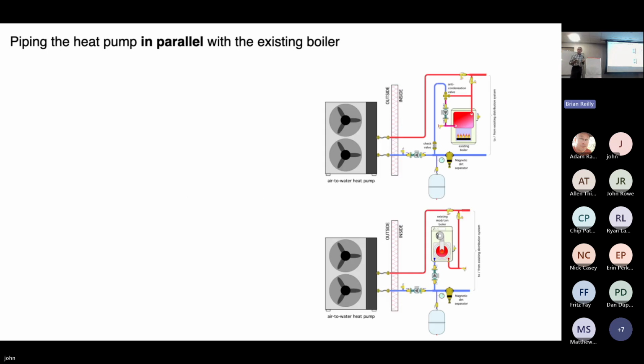John, may I ask a quick question? Sure. Maybe not quick, but if we can't get to it now, I'd love to address it at some point. You showed a slide. We have these dual fuel systems. So we're keeping the boiler, we're adding an air to water heat pump. And we talked about a balance point. When the heat pump can't carry the load, then the boiler can come on. That would be a capacity balance point, supplemental heat. There's also a scenario where it's an economic balance point. At some point, it's cheaper to heat the home off of the gas boiler. At some point, it could be cheaper to heat the home from the heat pump.